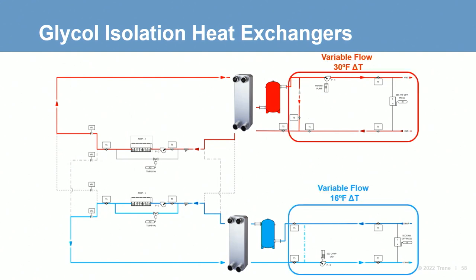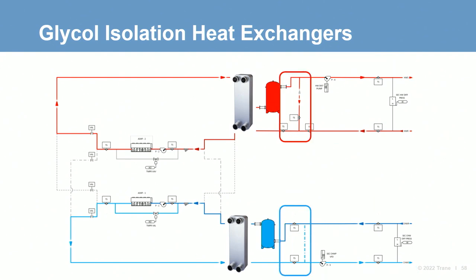These are standard distribution loops and may be optimized for the supply temperatures, flows, and delta T's as required by the airside design. The airside coil capacity may be controlled with two-way valves, causing widely variable distribution pumping flow for both the chilled water and heating water distribution. This provides for significant operational flexibility and opportunities for pumping energy savings. At the heart of the system are the decoupler lines. They provide the hydronic isolation that allows for optimization of flows and temperatures in both the distribution and production loops.